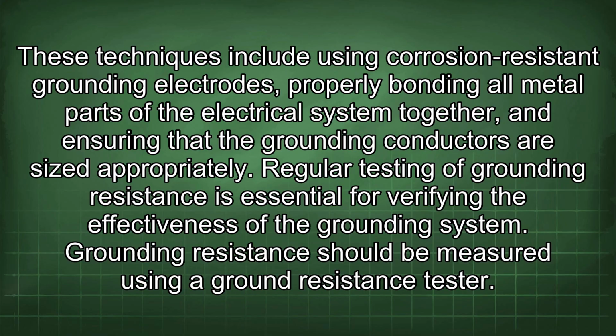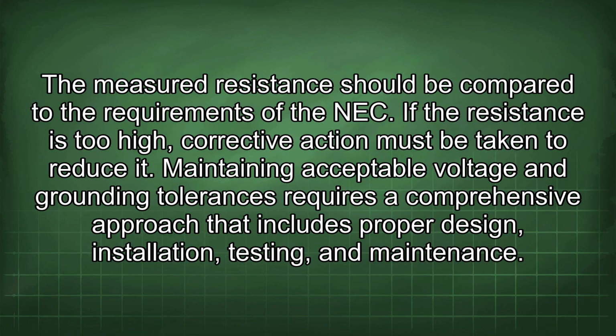Regular testing of grounding resistance is essential for verifying the effectiveness of the grounding system. Grounding resistance should be measured using a ground resistance tester. The measured resistance should be compared to the requirements of the NEC. If the resistance is too high, corrective action must be taken to reduce it.